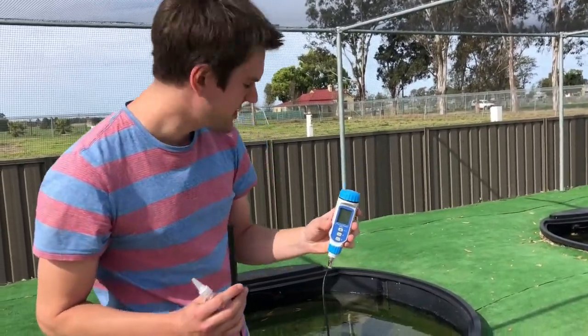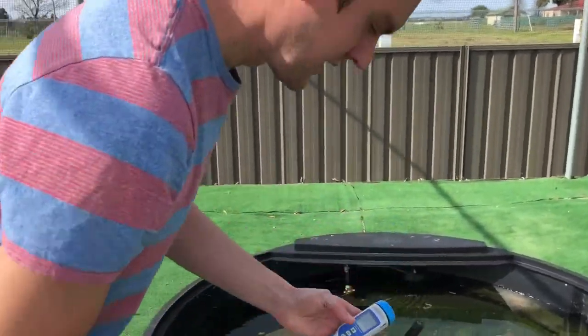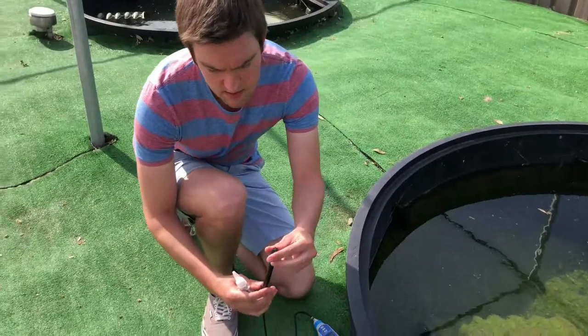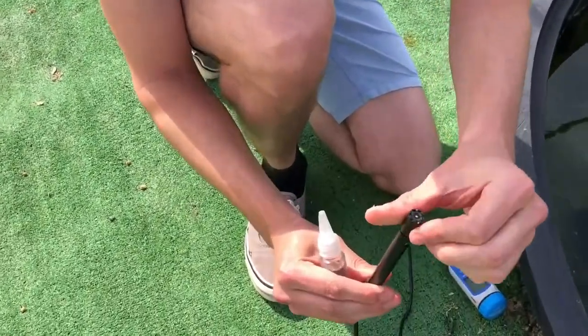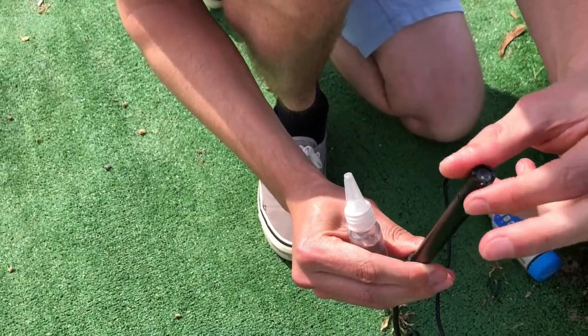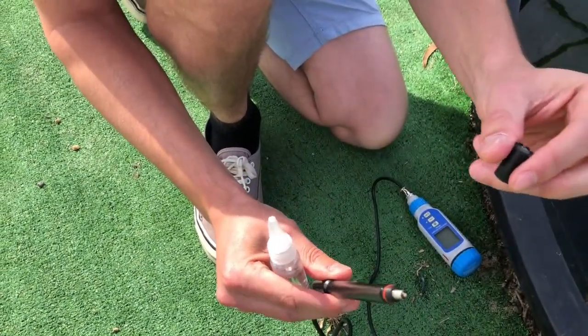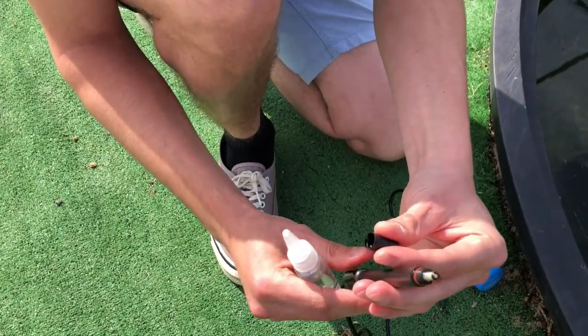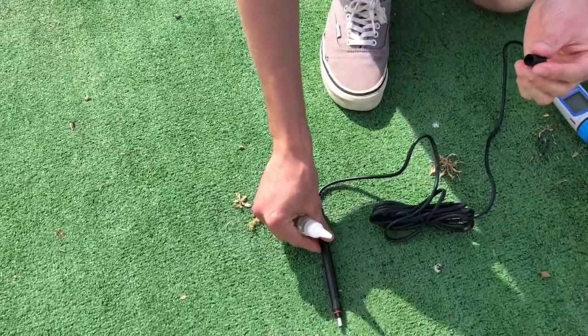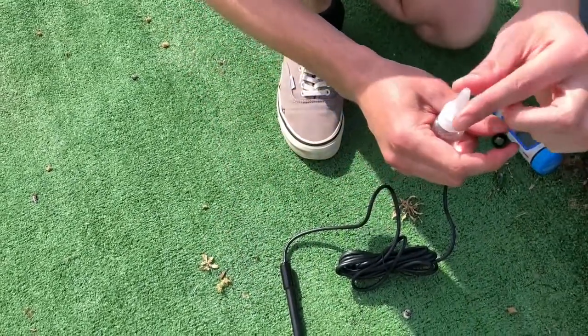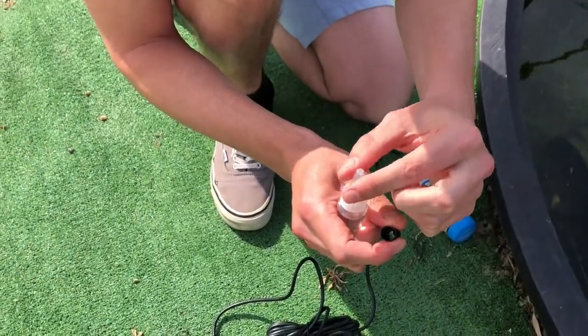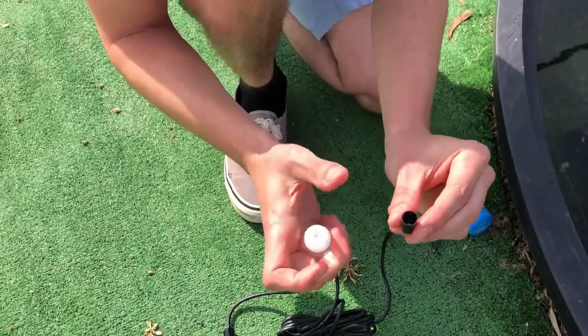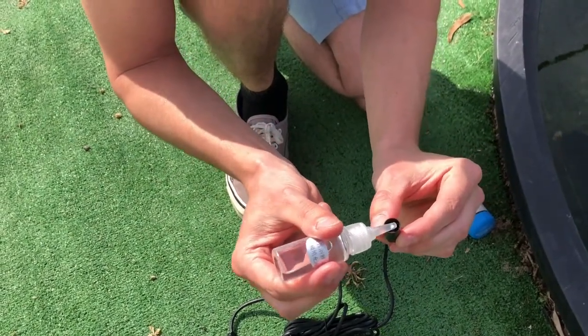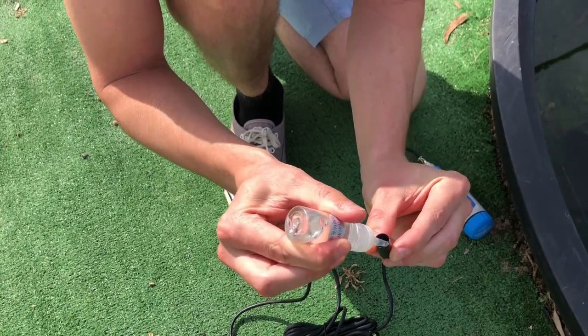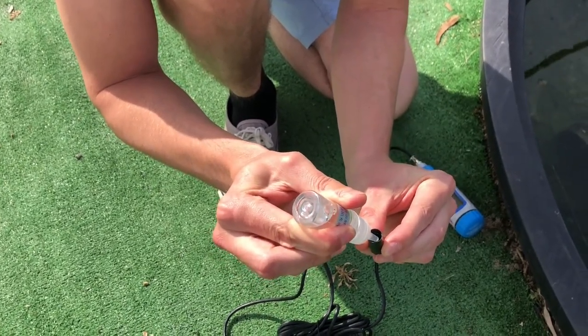Now we're going to run through how to use the meter in a pond that we've got here. So we'll just come over. Okay, so the first thing to do is unscrew the probe head. And what we need to do now is gently put the probe down so it's not damaged.